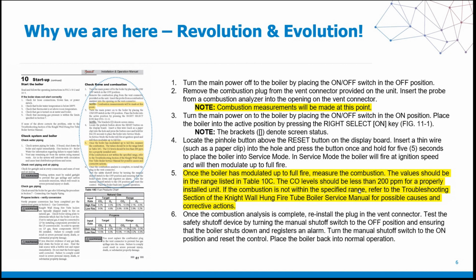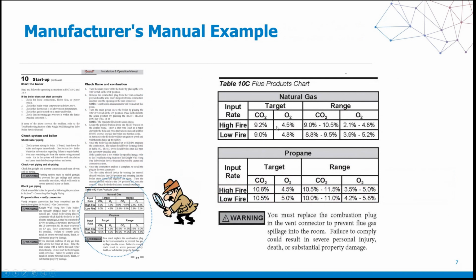And it's in the manuals, like you see here, where it shows combustion measurements will be made at this point. They're putting this in the manuals because not only do they want you to test, they're also requiring you to test. And you could see it here as well. CO2 targets, O2 targets for high fire and low fire that I've highlighted here. So that manual that you keep in your truck and that you pull out because it's nice and thick and you need an additional knee pad, well, there is very important information in the bowels of that manual that actually states what your combustion parameters are supposed to be, and that is what the manufacturers want you to follow.